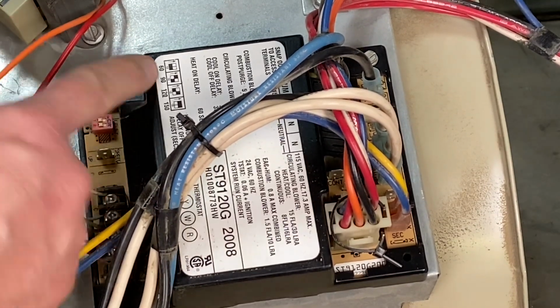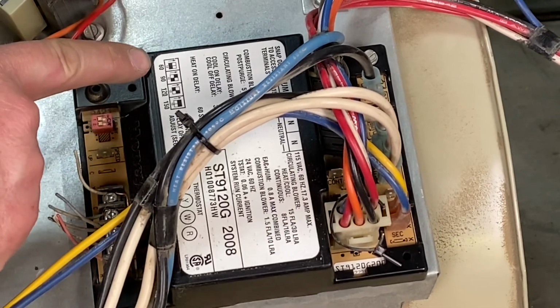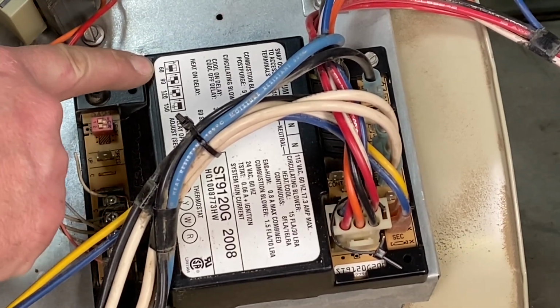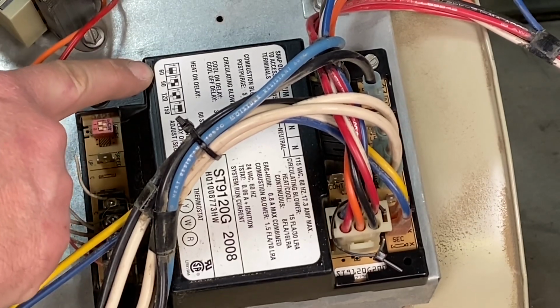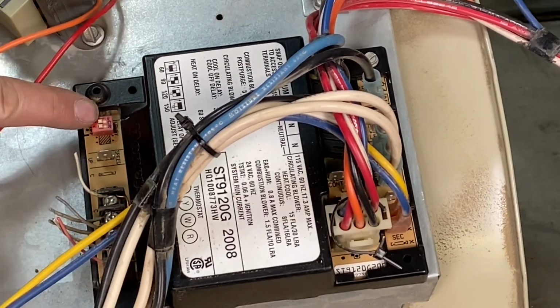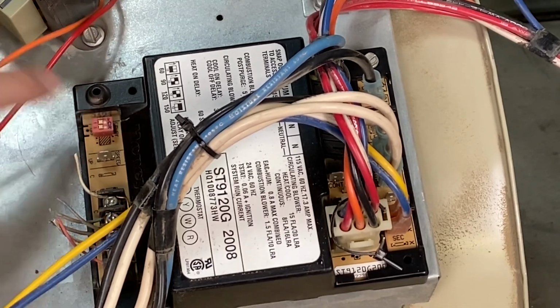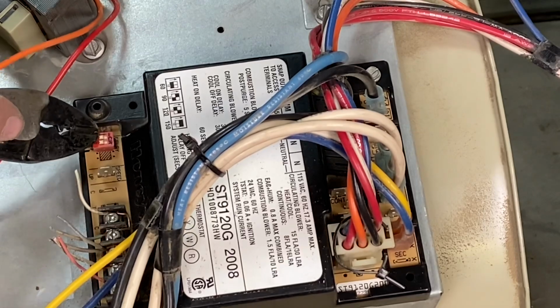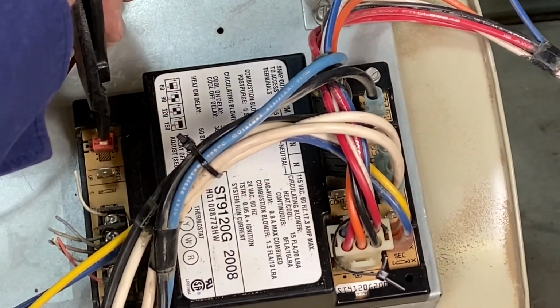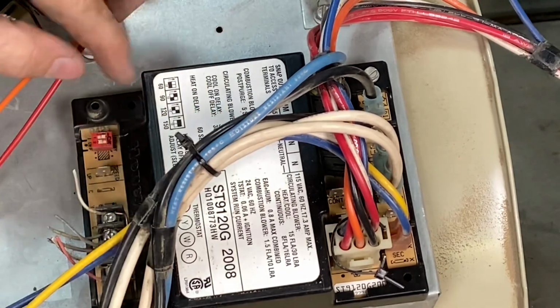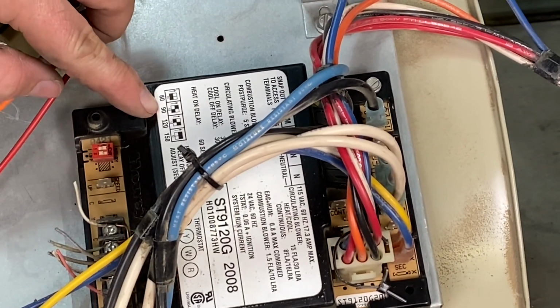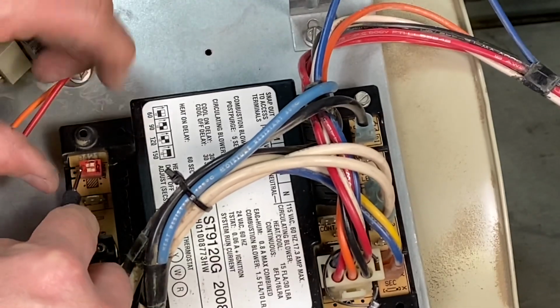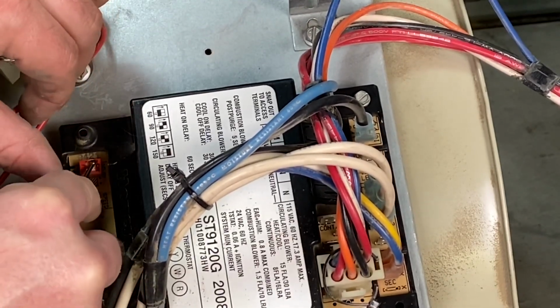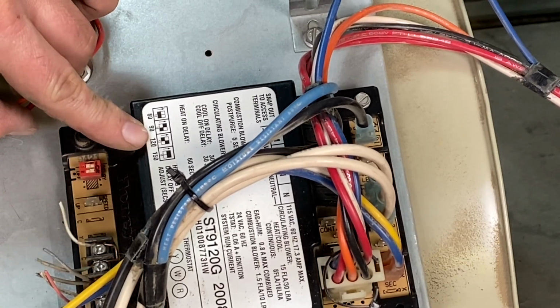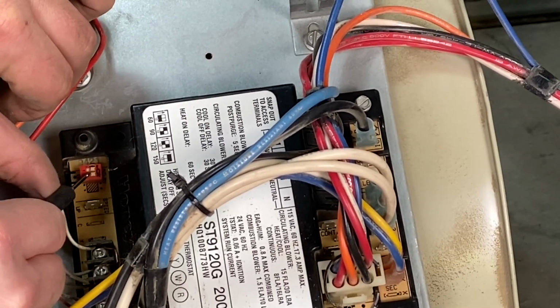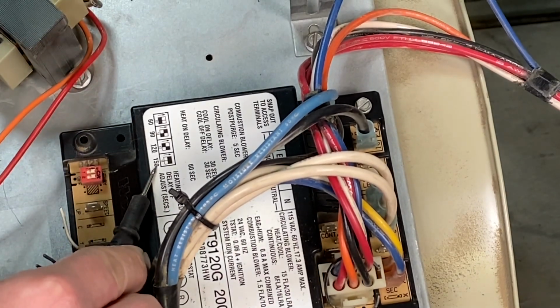So the different patterns, if I have them both down, which like it is now, it has an off delay of 60 seconds. So that means after the flames end, the blower stays on for 60 seconds. What's more efficient is if I was to push one of these forwards. If I moved this terminal forward, now it has a 90-second off delay. And another thing, if I wanted even more heat out of that, I would push where this one was up and this one was down. That'd give me a 120-second off delay. And if they were both all the way forward, that'd give me a 150-second off delay.